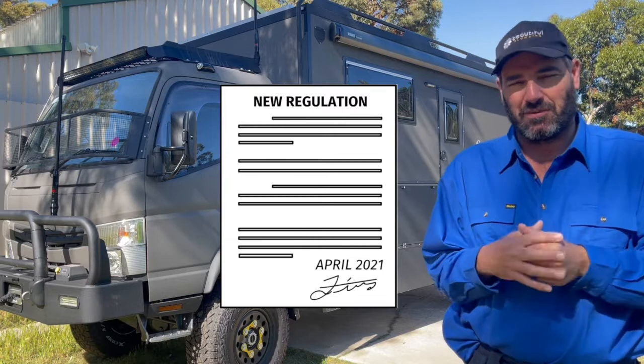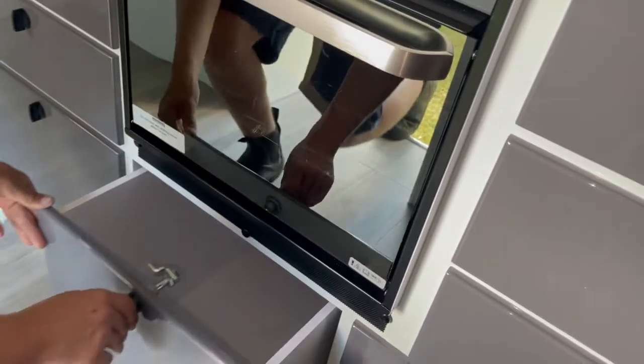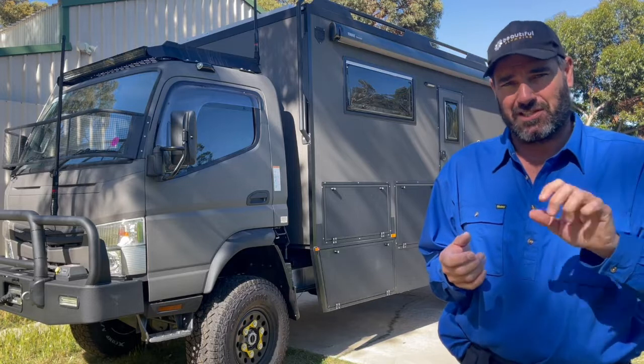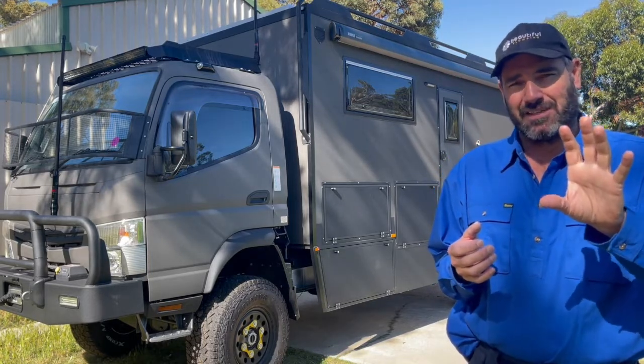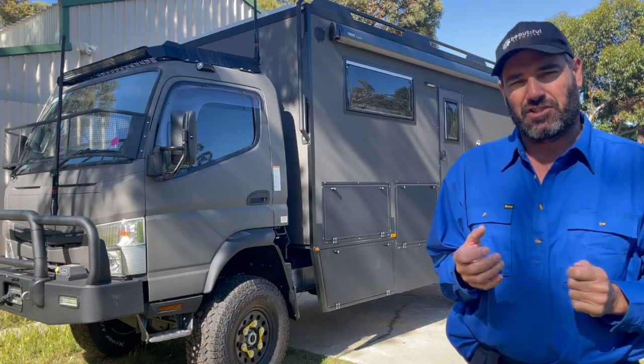The reason we've got to change those over is because of new regulations back in April 2021. So just a few stickers sorted. The gas isolation valve for the hot plate needs to be in an accessible location, and it's not — it's behind one of these drawers, like filing cabinet drawers, quite difficult to take out. Most people don't know how to get them out, so in an emergency you need to be able to reach it and turn it off. What we're going to do is leave that one in place and just put a new one in one of the lockers below so it's very easy to shut off.